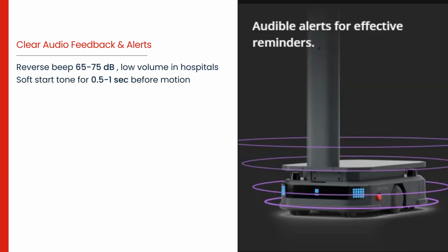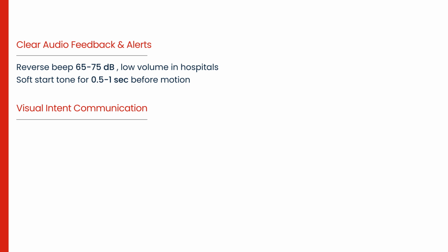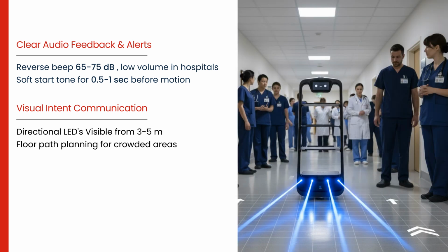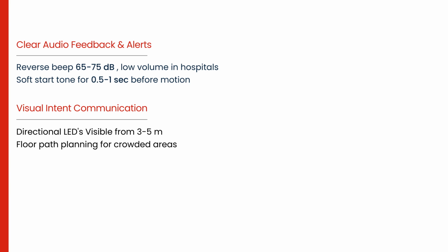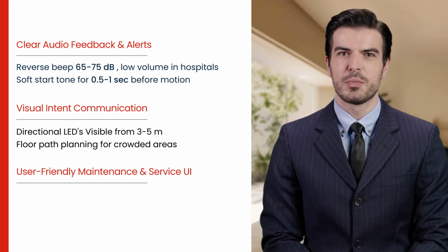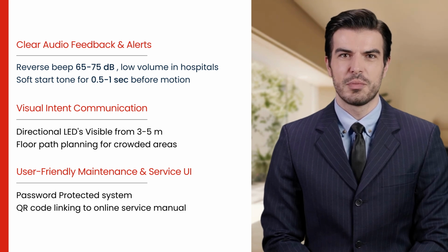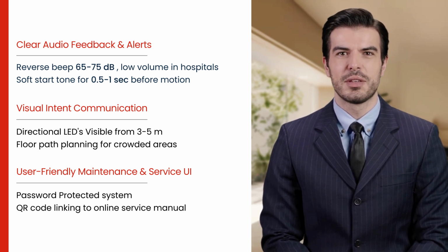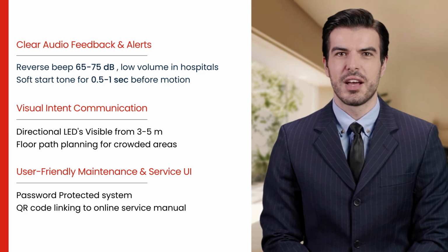The robot must provide unmistakable sound cues: soft startup tones, reverse beepers, and voice prompts like "robot turning" for around 0.5 to 1 second, with adjustable volume modes of around 65 to 75 decibels for night or hospital use. The robot must clearly show its movement intentions using directional LED arrows, floor path projection lights, and pre-movement scanning animations to indicate turning, reversing, or docking actions. The service interface must support fast diagnosis with a dedicated technician menu, QR codes linking to manuals, and on-screen error descriptions with detailed logs.